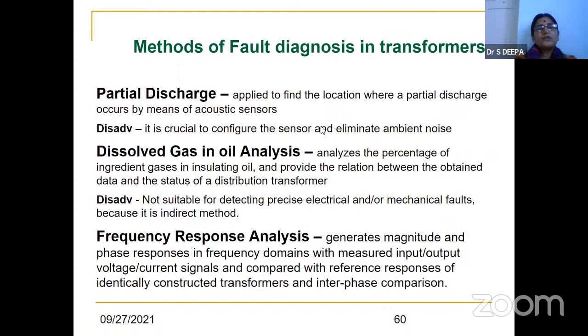So basically, the distribution transformer is here. I had taken it up. So what are the methods for fault diagnosis? Partial discharge, dissolved gas in oil, and frequency response analysis. Partial discharge is applied to find the location, where a partial discharge is detected by means of acoustic sensors, and it is crucial to configure the sensor and eliminate ambient noise.